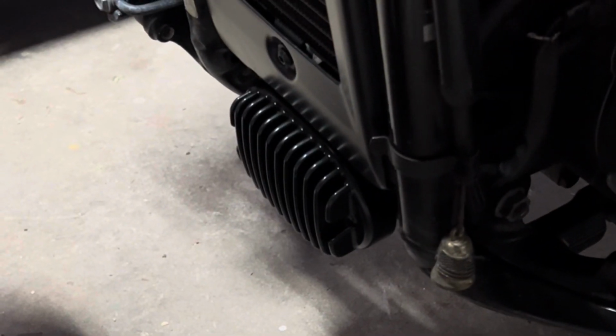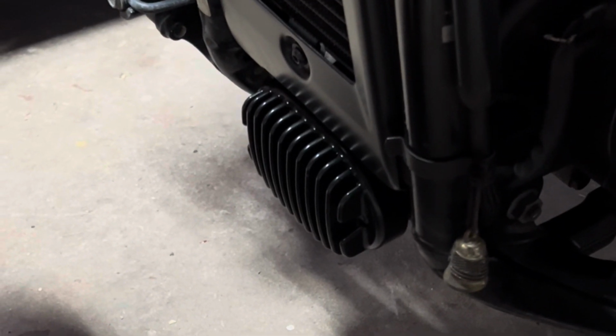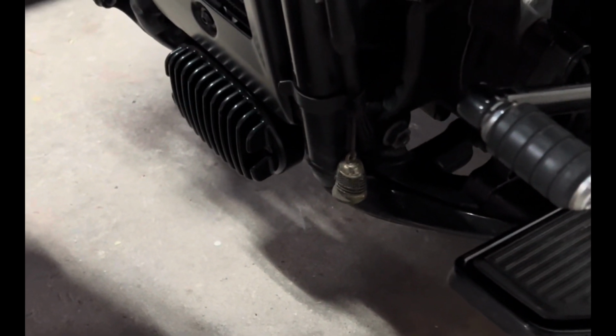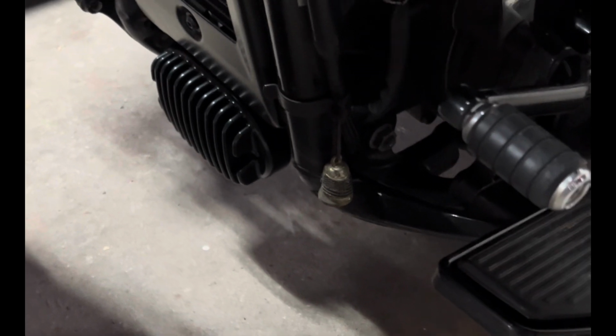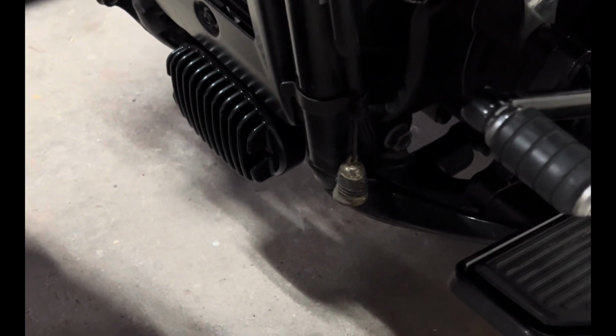You'd think it just reduces the voltage, but what it actually does is use a thyristor, turning it on and off so it reduces the amount of voltage coming through to the rectifier. It does this multiple times a second, so in the end you won't see it at all, but it results in a steady state value down to the correct regulation for your battery charge requirements.